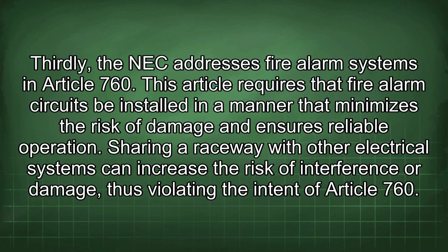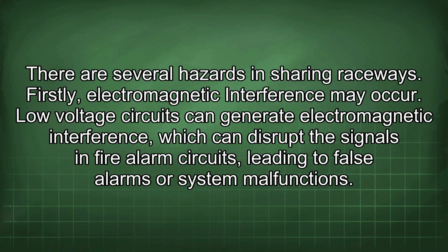Thirdly, the NEC addresses fire alarm systems in Article 760. This article requires that fire alarm circuits be installed in a manner that minimizes the risk of damage and ensures reliable operation. Sharing a raceway with other electrical systems can increase the risk of interference or damage, thus violating the intent of Article 760. There are several hazards in sharing raceways.